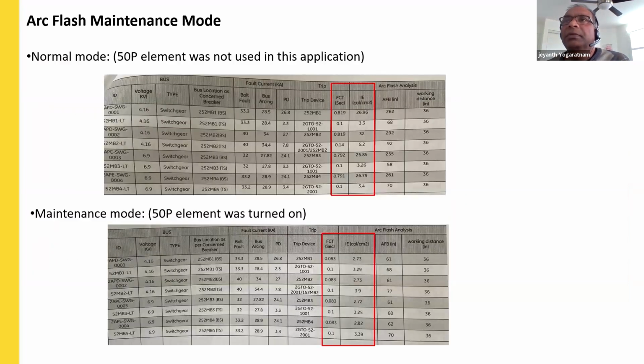So this is the comparison of arc flash incident energy between the normal mode and the maintenance mode. During the normal mode, in this particular application, the 50P element was not enabled. Only the 51 element was enabled, and we can see here the fault clearing time was 819 milliseconds, and the arc flash incident energy was about 27 calories per centimeter squared. Once we put it into the maintenance mode and the engineer enabled the 50P element with zero time delay, the fault clearing time went down to 83 milliseconds, and the incident energy went down to 2.73. So this is what is expected from this application.